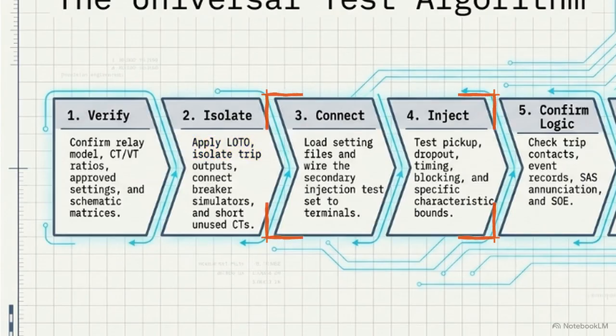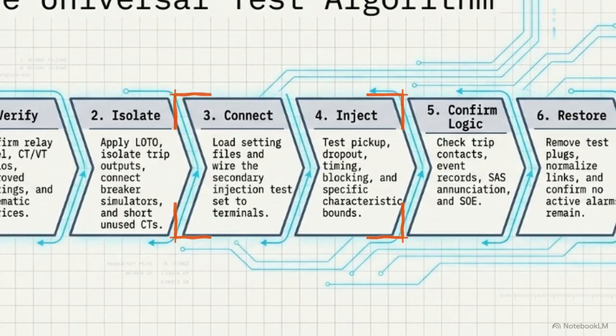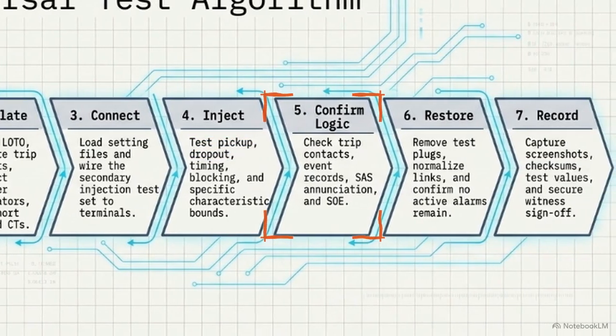Steps 3 and 4 are connect and inject. Technicians wire a calibrated secondary injection test set, multimeters, and binary input-output leads to the isolated terminals. They then inject controlled secondary currents to test the relay's performance against specific characteristic bounds. Step 5 is confirming logic. As the injection set pushes the relay past its thresholds, technicians verify that the unit accurately toggles trip contacts, engages mechanical lockout paths, and triggers the substation automation system annunciation with an accurate timestamp.